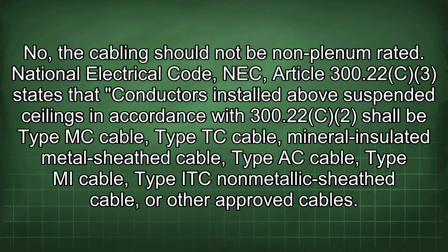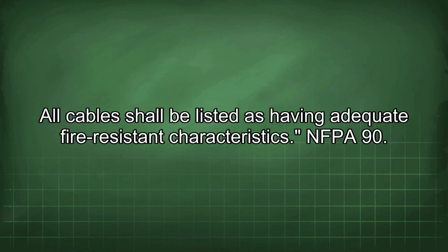The cabling should not be non-plenum rated. National Electrical Code (NEC) Article 300.22(C)(3) states that conductors installed above suspended ceilings in accordance with 300.22(C)(2) shall be Type MC cable, Type TC cable, mineral insulated metal sheath cable, Type AC cable, Type MI cable, Type ITC non-metallic sheath cable, or other approved cables. All cables shall be listed as having adequate fire-resistant characteristics.